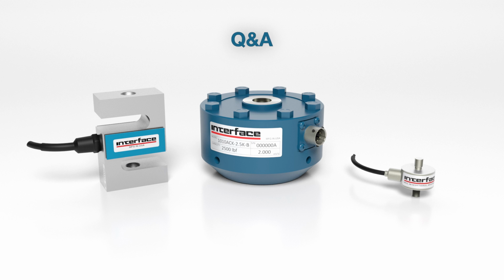Okay, next question. How do you pick your points for calibrating a load cell? For example, a 10K load cell, 2,000, 4,000, etc. Typically, on a low-profile series like that, you're going to have 20% points in tension and compression. So it's going to go 5 up, 1 down for your hysteresis point. Other load cells are going to have some different calibration options. The SM series is going to have a standard tension calibration.